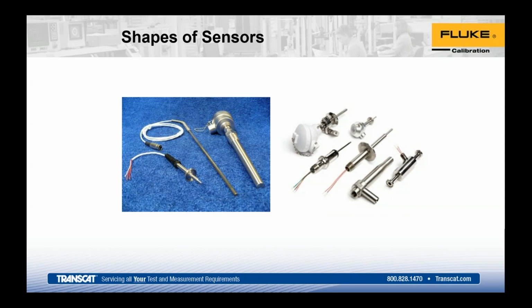Typically, for short or uniquely shaped sensors, a bath is a better option. It provides a lot more flexibility, and you're going to get a lot more thermal conductivity with the fluid. In this picture you can see a more traditional PRT probe, typically an 1/8, 3/16 or 1/4 inch diameter and sheathed anywhere from 6 to 12 inches, which is the most common. So again, things to think of there.